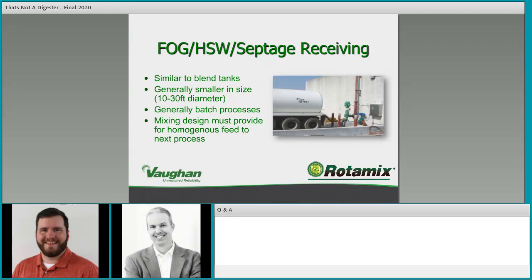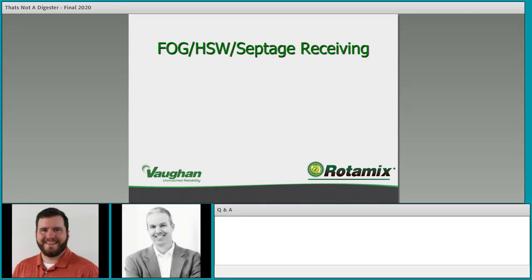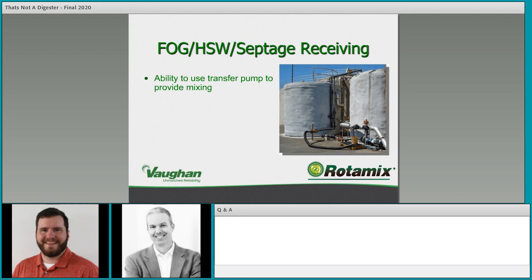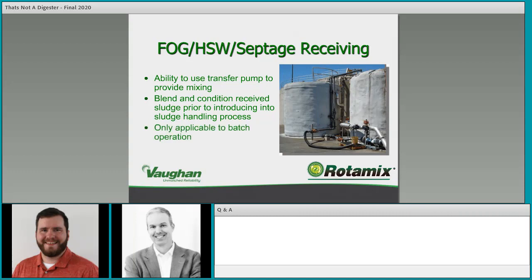Your mixing design must provide for homogeneous feed to the next process. If you're feeding a blend tank, you don't want to hit it with a slug of something nasty — you want to blend it as much as possible and make sure you're cycling through your batches. We provide externally mounted adjustable stainless steel nozzles that can be mounted to the external piping of a tank, especially useful for above-ground small fabricated tanks — steel or poly. The pump can also be used as a transfer pump.